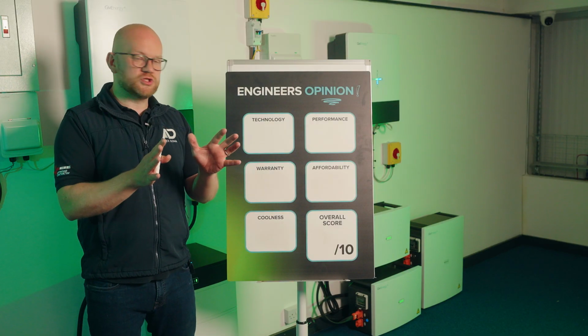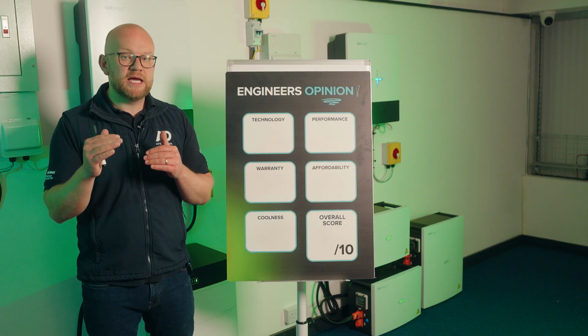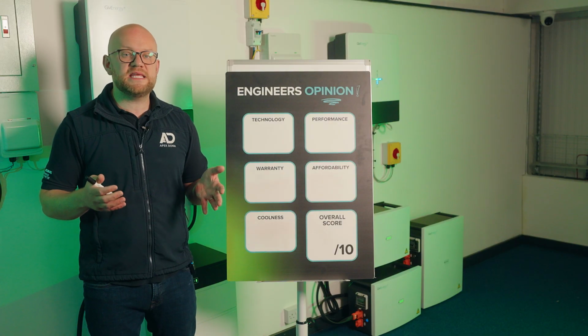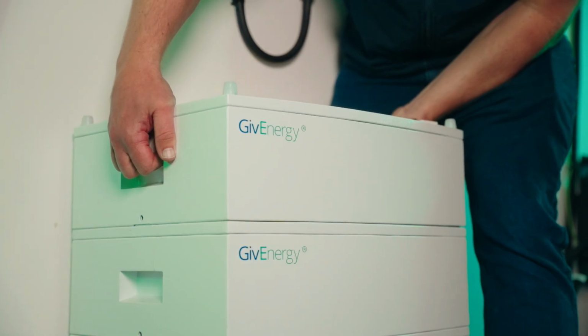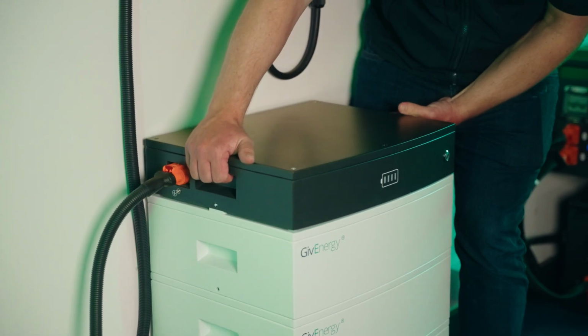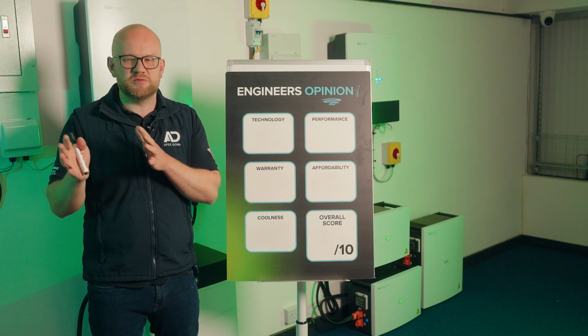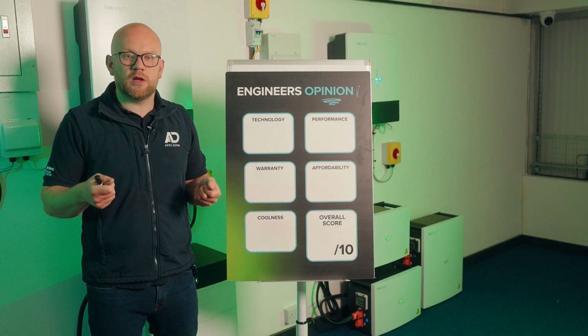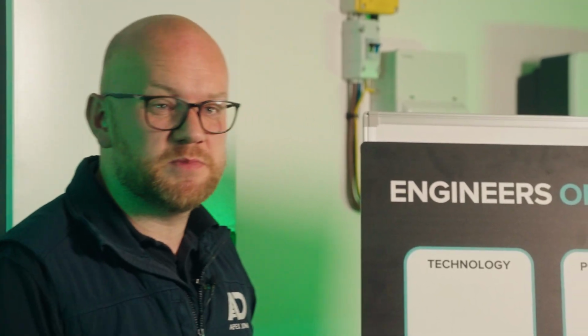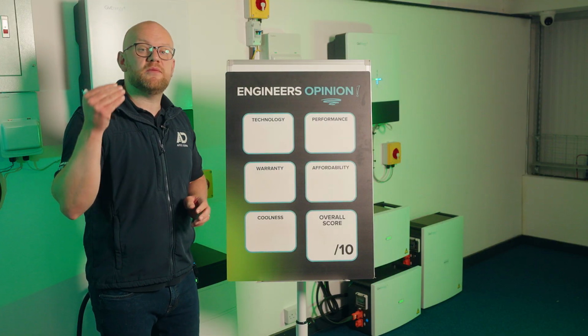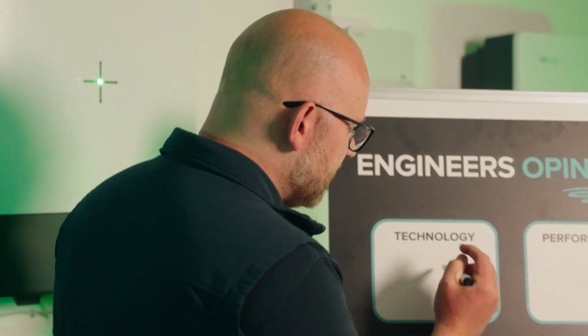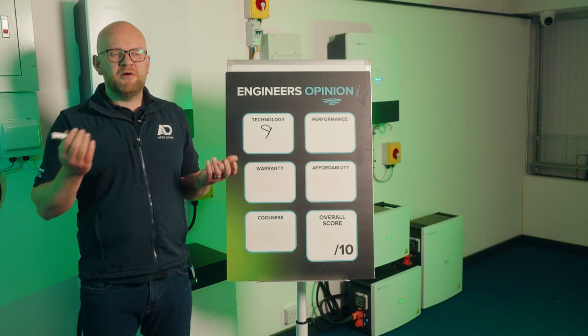On the low voltage range, I rated the technology an 8. I'm going to go a little higher for the high voltage stackable battery range, to a 9, and I'll explain why. Within this technology, they've created the ability to add extra batteries in a really straightforward way. At low voltage, you can add extra batteries, but it's the fact that you do it in 3.4 kilowatt hour increments that makes it much more straightforward from an engineer's perspective, and for you as an end user, you don't need to be so capital heavy. So I'm giving technology a solid 9.